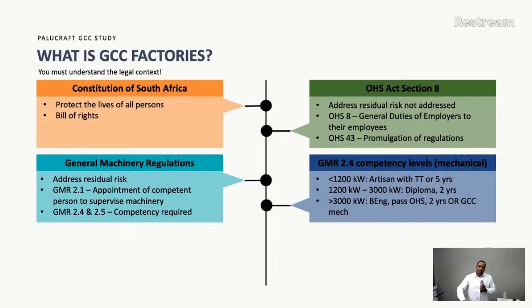So the law says if the sum of the power generated by the factory is below 1,200 kilowatts, an artisan with a trade test can become a GMR 2.1 appointee. If it's between 1,200 and 3,000 kilowatts, then you need a diploma in mechanical or electrical engineering plus 2 years operation and maintenance experience in the class of machinery that you are meant to supervise.